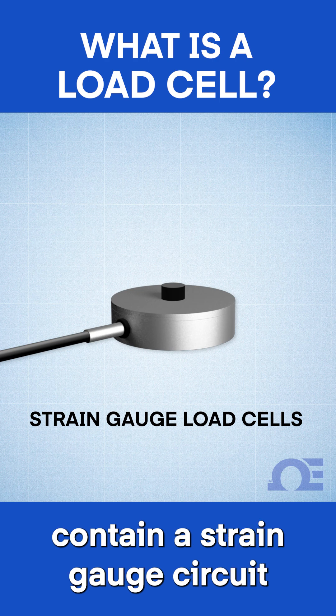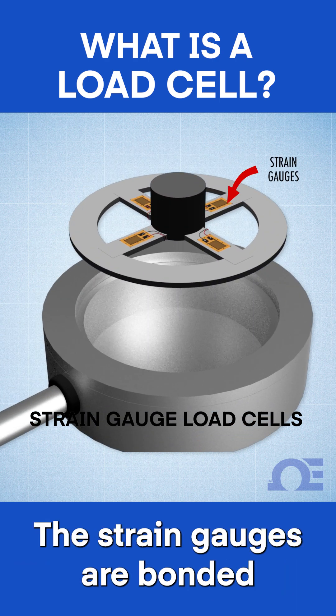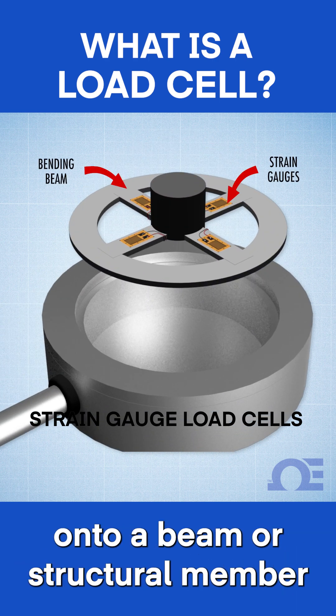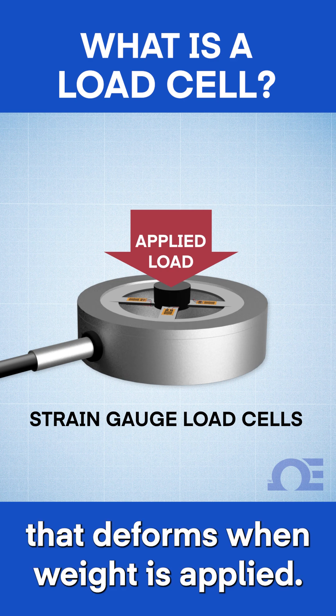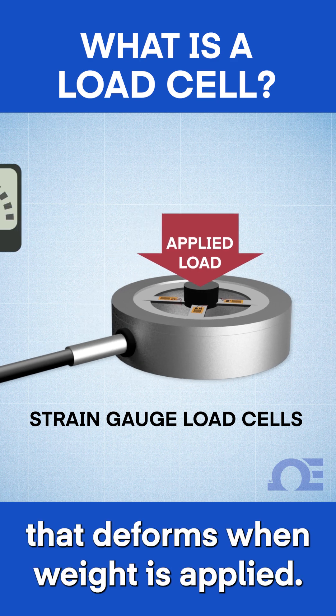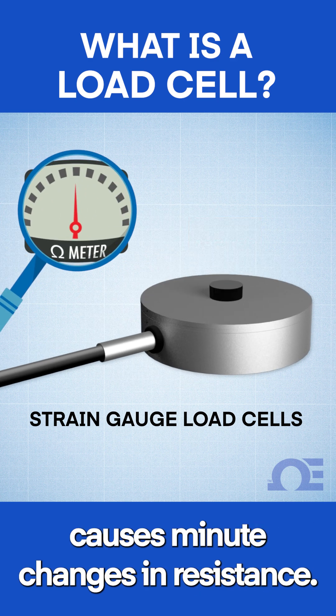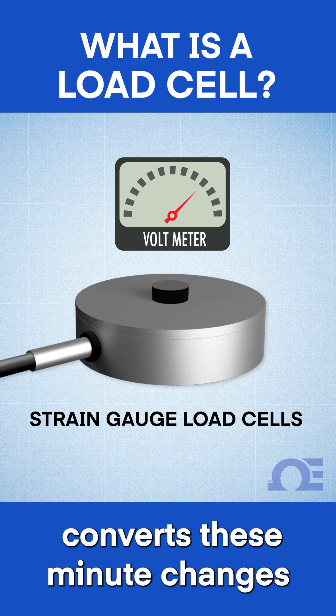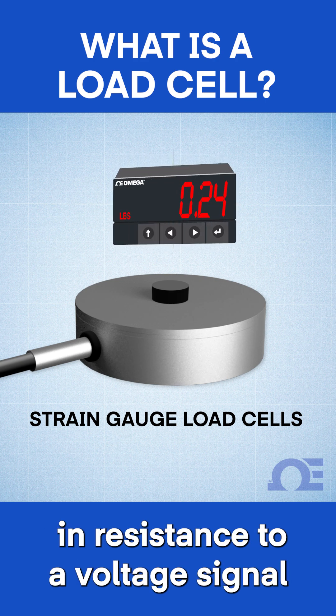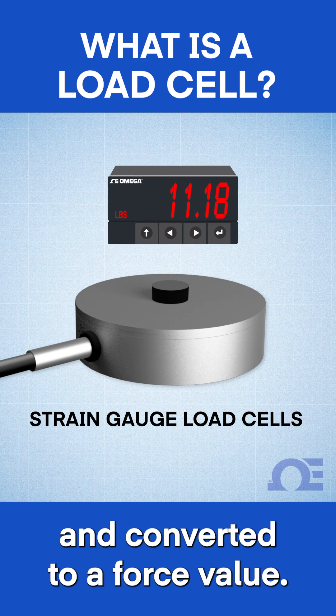Strain gauge load cells contain a strain gauge circuit known as a Wheatstone bridge. The strain gauges are bonded onto a beam or structural member that deforms when weight is applied. The deformation of the strain gauges causes minute changes in resistance. The Wheatstone bridge circuit converts these minute changes in resistance to a voltage signal that can be accurately read and converted to a force value.